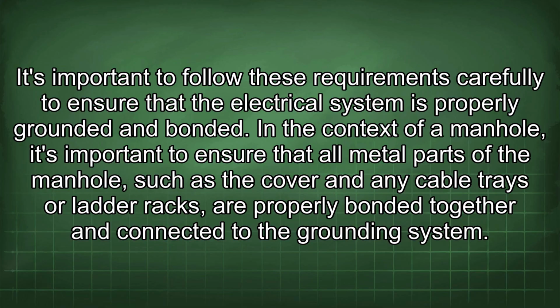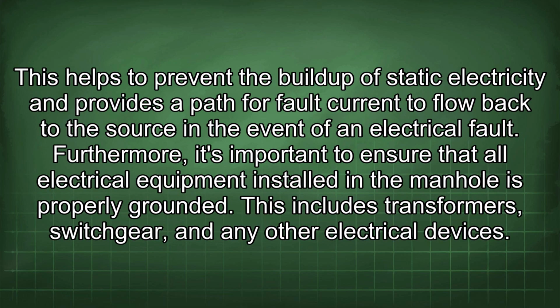In the context of a manhole, it's important to ensure that all metal parts of the manhole, such as the cover and any cable trays or ladder racks, are properly bonded together and connected to the grounding system. This helps to prevent the buildup of static electricity and provides a path for fault current to flow back to the source in the event of an electrical fault.